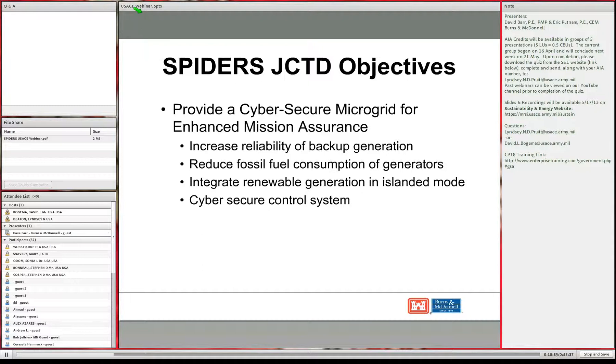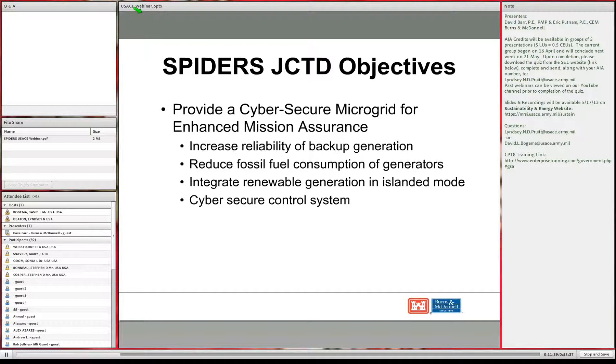SPIDERS also reduces fossil fuel consumption of generators. It's not uncommon for a diesel generator to be sized conservatively—perhaps for a peak or future peak demand—and under average operations it runs at significantly less than its design load, meaning 20 to 70 percent of design capacity, which is a less efficient point on the fuel consumption curve. The SPIDERS configuration balances the fewest number of generators to serve the greatest number of loads in a way that optimizes fuel consumption, reducing both costs and logistical burden.